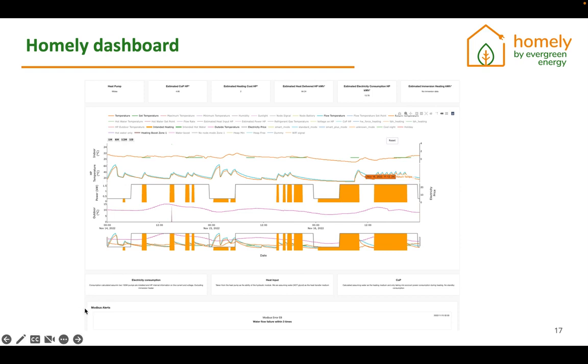Most importantly, there are also the Modbus alerts at the bottom. Over here, you can see when the Modbus alert was thrown. This is an alert that is coming up on the heat pump, and here you can also see what it means. So if the customer calls up and says that they don't have heating, you go into the dashboard and check if there are any errors being thrown, and this could help you identify an issue and the parts that you need to bring to site to fix the problem.